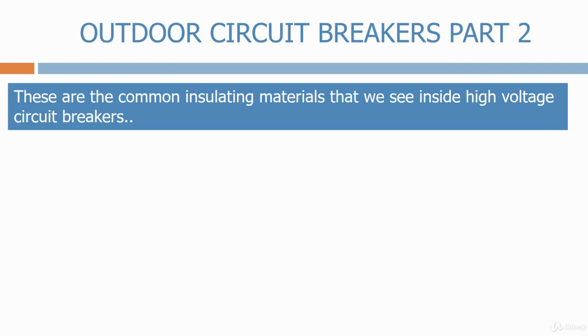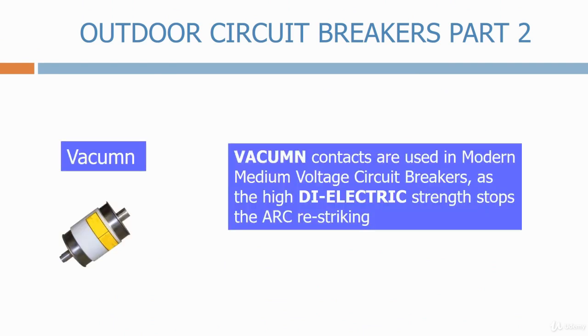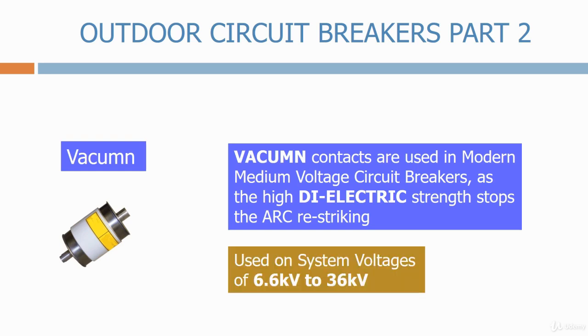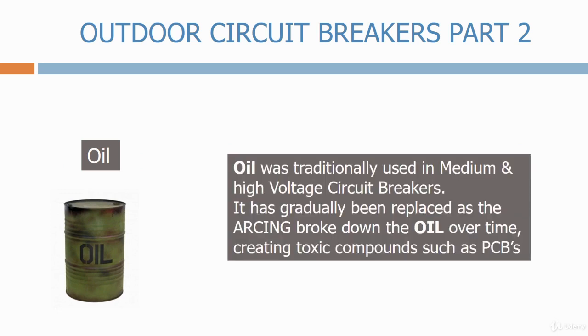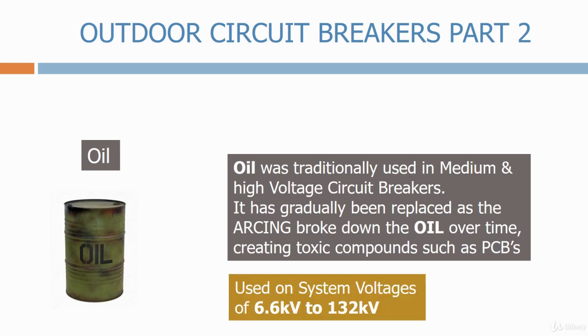These are the common insulating materials that we see inside high voltage circuit breakers. Vacuum. Vacuum contacts are used in modern medium voltage circuit breakers, as the high dielectric strength stops the arc restriking. It's used on system voltages of 6.6 kV to 36 kV. Oil. Oil was traditionally used in medium and high voltage circuit breakers. It has gradually been replaced, as the arcing broke down the oil over time, creating toxic compounds such as PCBs. It's used on system voltages of 6.6 kV to 132 kV.